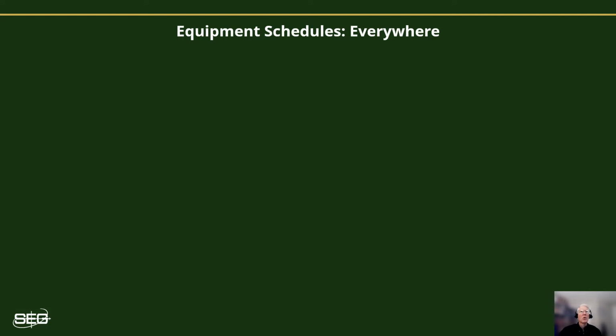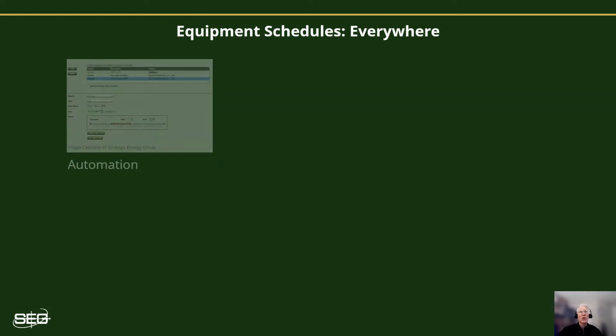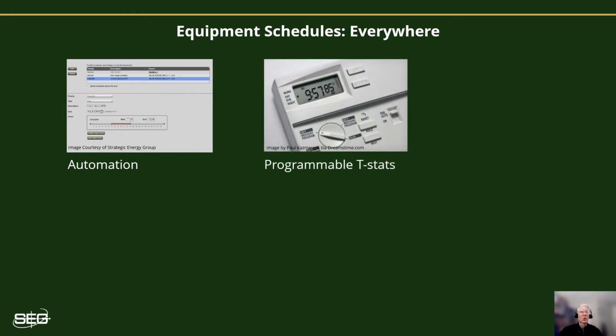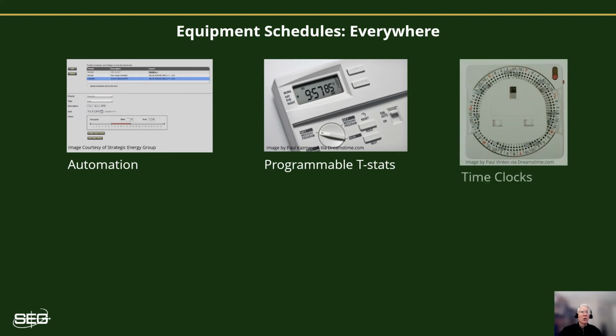Let's talk about equipment schedules now. Whether you have a state-of-the-art building automation system, an older pneumatic control system, programmable stats, or even simple time clock controls, it's very important to check and verify what the actual operating schedules for the building's equipment are currently set for. Depending on how comprehensive or rudimentary the control systems are, it may involve checking in multiple locations.